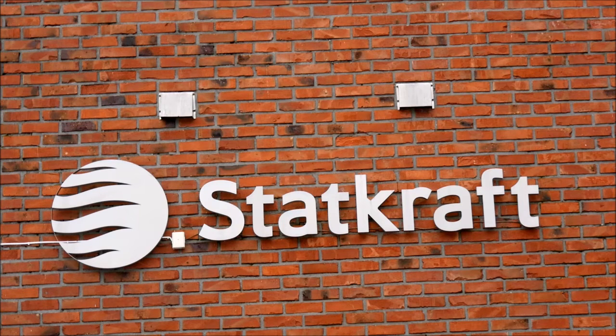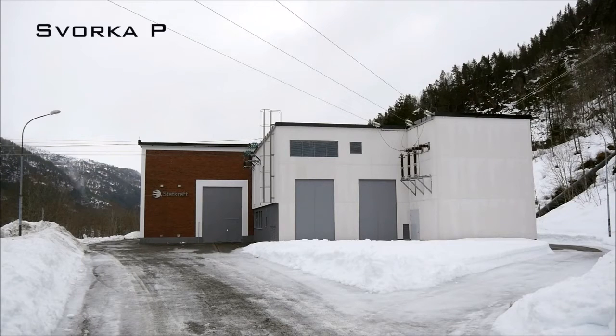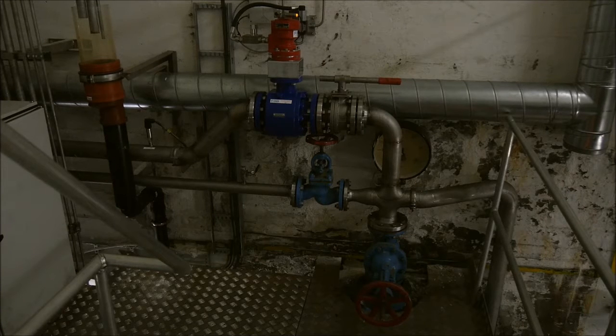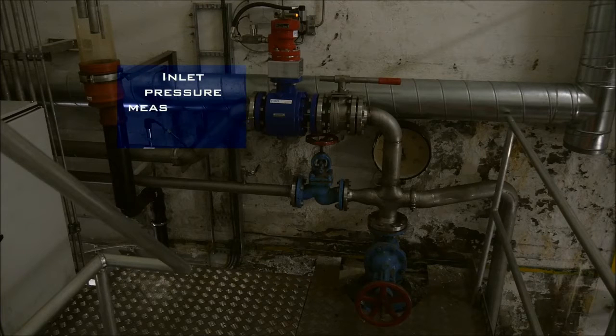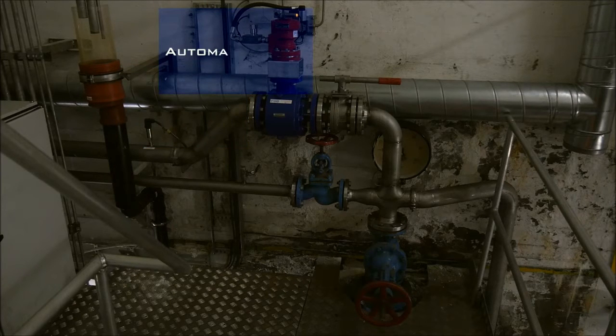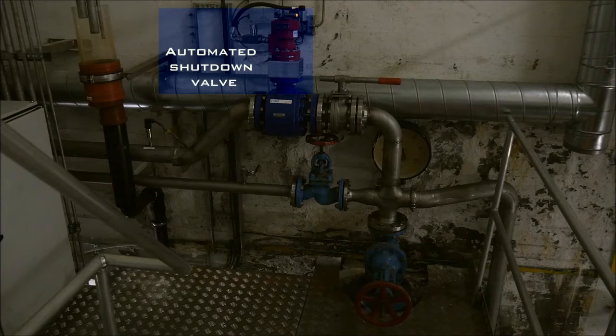Statkraft's involvement started in 2009, as a cooperation project was launched with Tromskraft and Flow Design Bureau. The goal was to develop two auxiliary systems. The first one, a protective system. The injected water is highly pressurized, and an eventual leakage or waterway failure has to be detected and immediately countered.